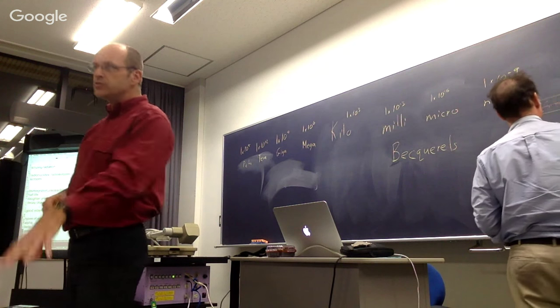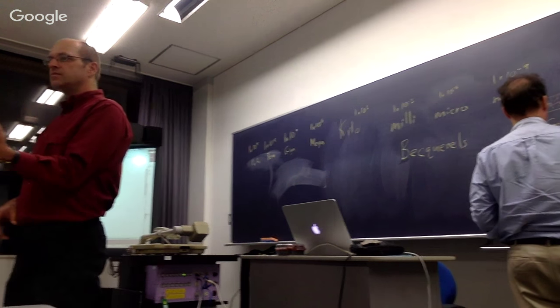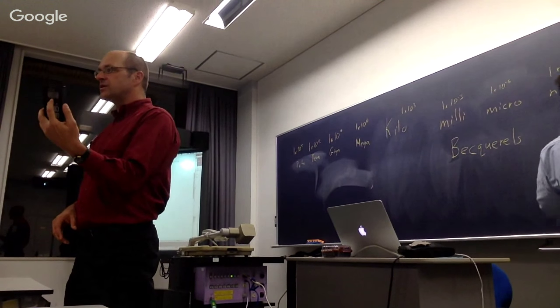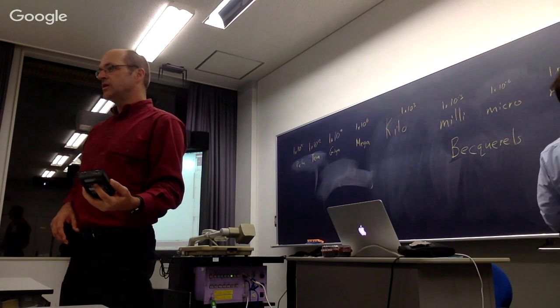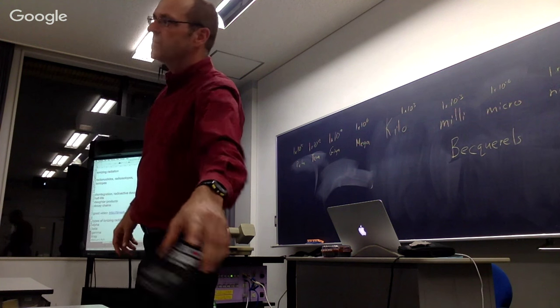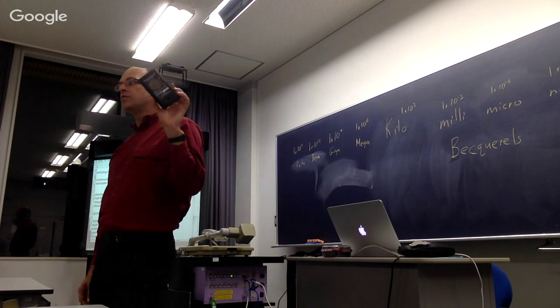So the actual dose rate that we convert from this, look, this is displaying in counts per minute, CPM. That's just the number of events. In order to convert that to a dose rate, you need to know what the source is. In fact, using this strontium source at a reading of 16,000, it would not give an accurate dose reading because this has been calibrated for cesium.